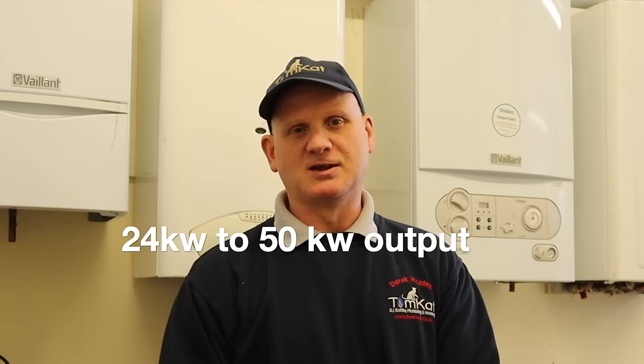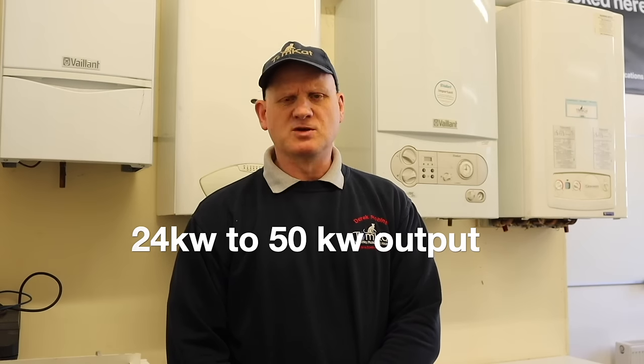Now, choosing the right size of combi boiler or combination boiler can be quite bewildering for homeowners and newly qualified engineers. Combi boilers range in size from 24 kilowatts up to 50 kilowatts at the moment. As a rough estimate for a small flat, say a one or two bedroom flat with one bathroom, a 24 to 27 kilowatt boiler would be sufficient to give your hot water needs.